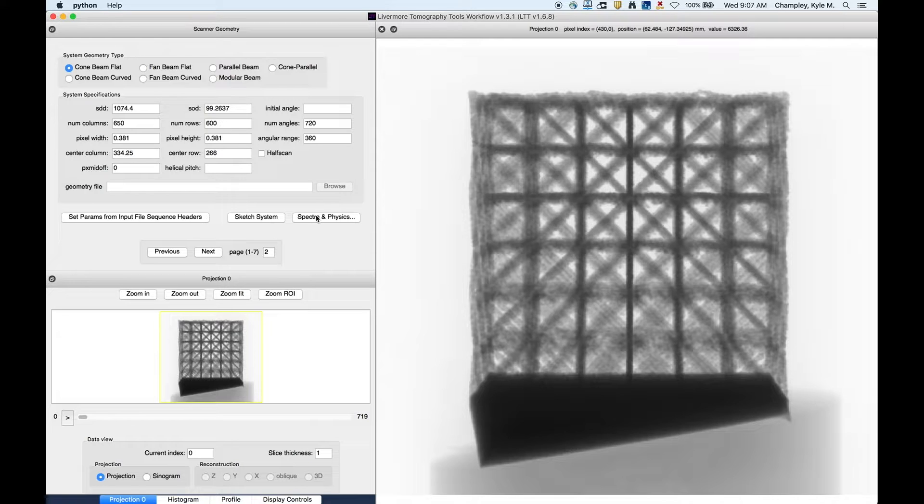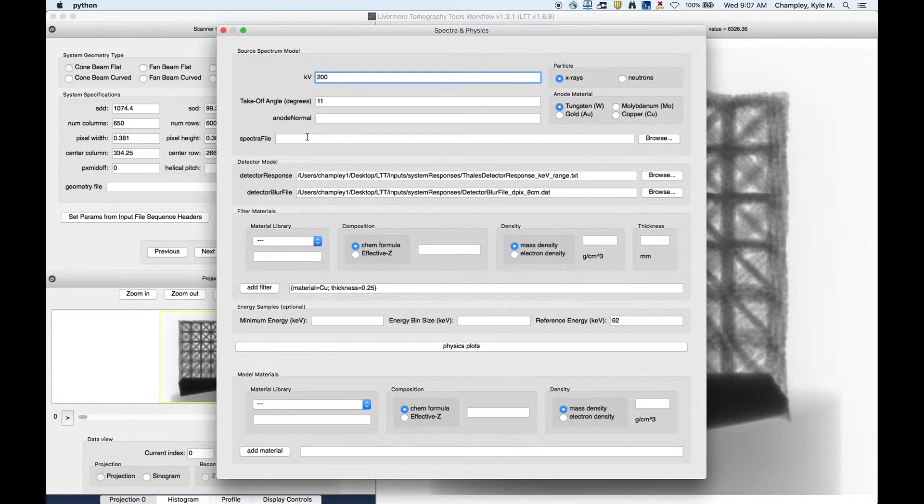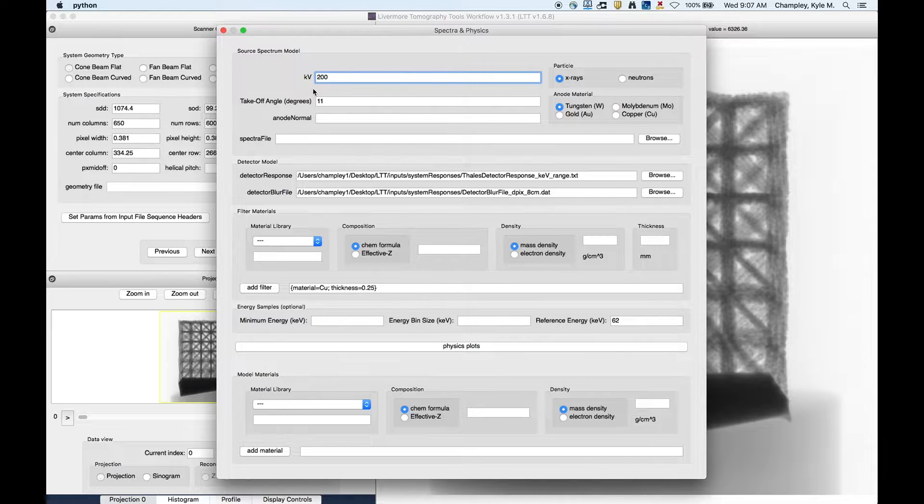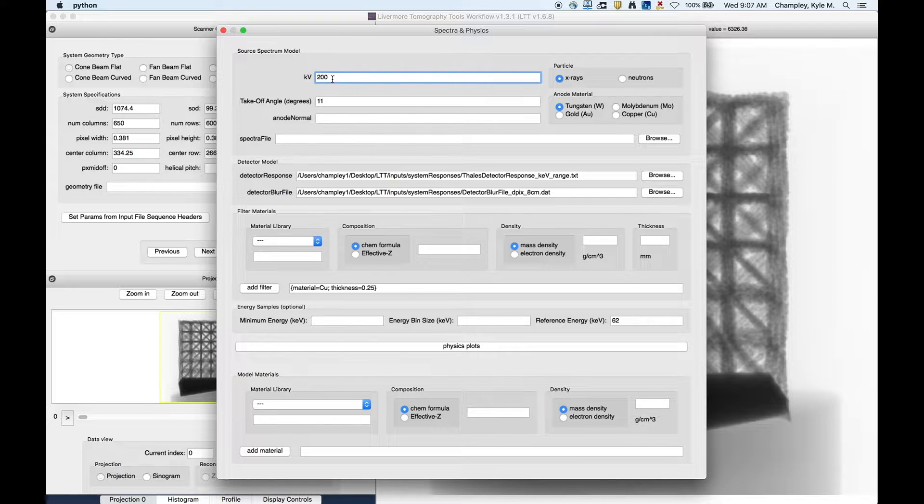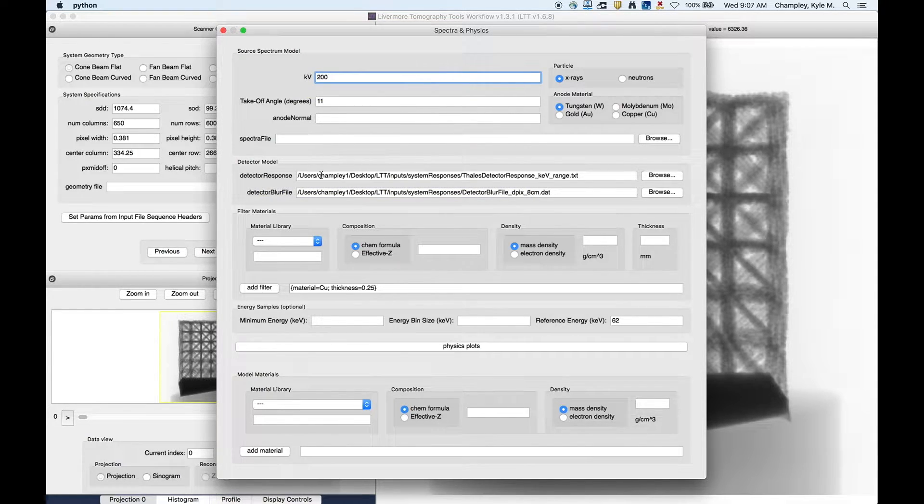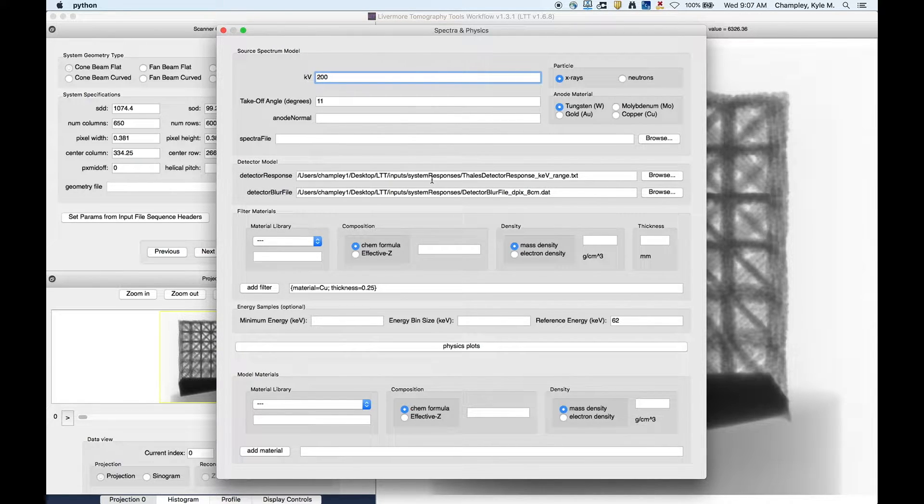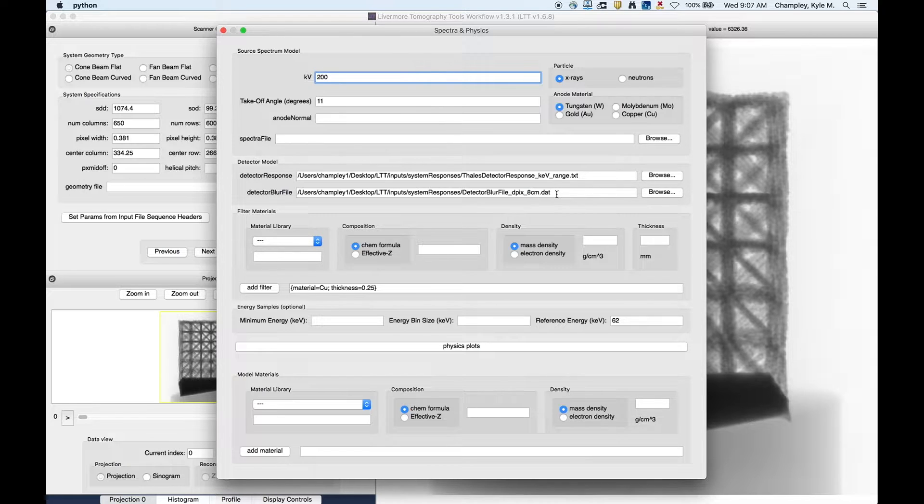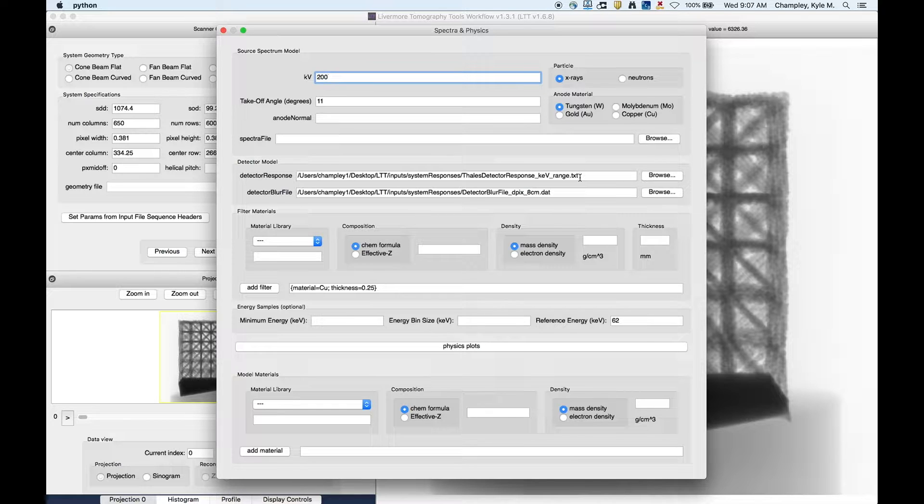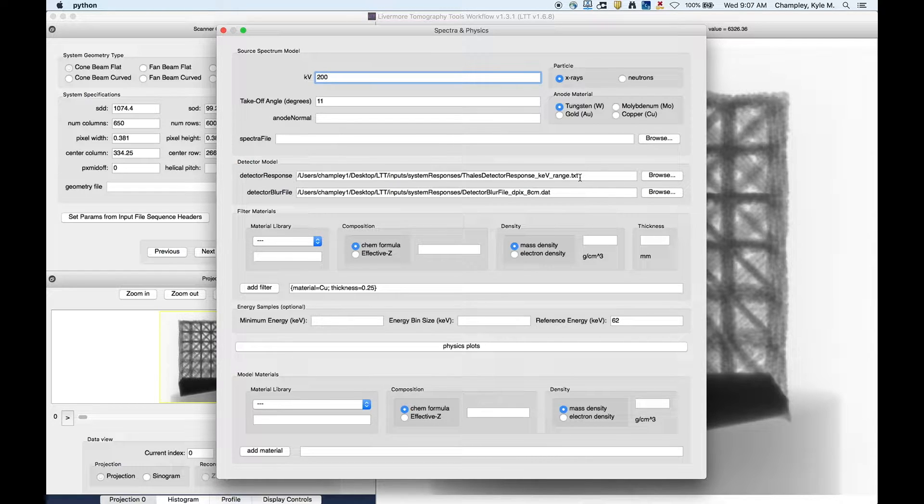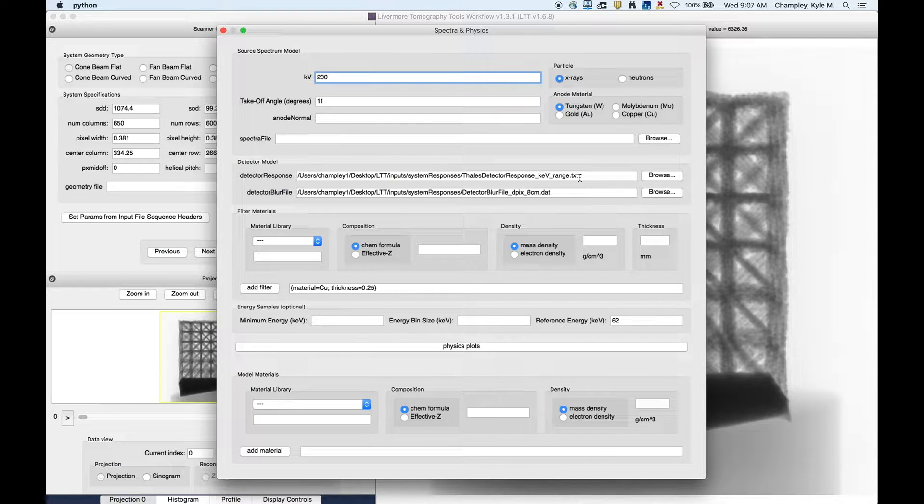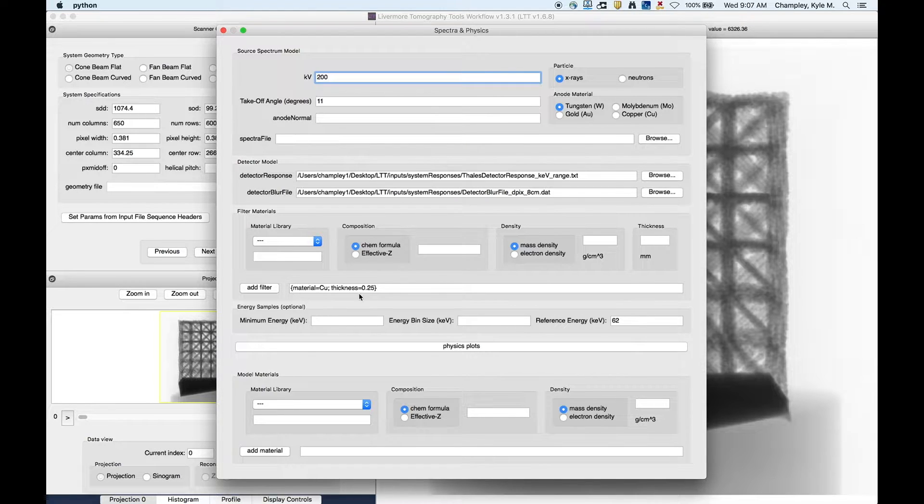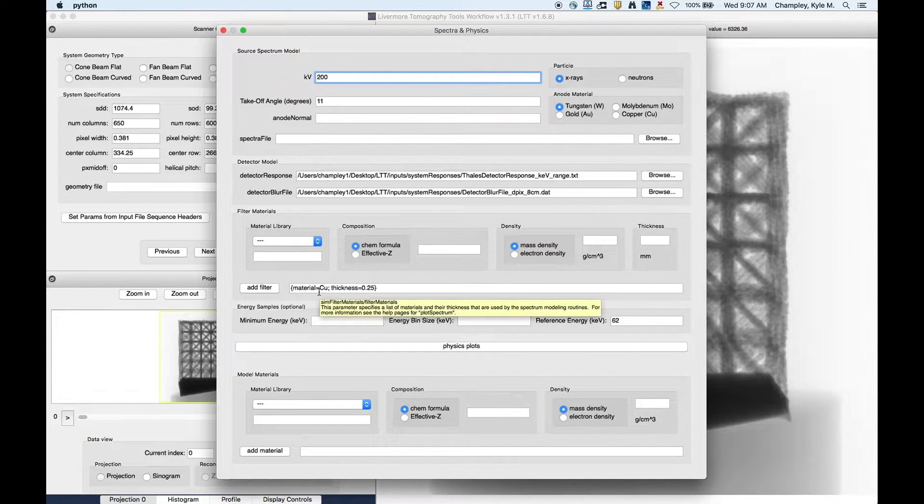We'll go to the next page, and now we're going to need to click on the spectra and physics button to make sure the entire spectra has been modeled. So here, the LTT did populate some fields. It populated KV, so it's a 200 KV. I actually put these in before, so I didn't have to find them. We have a detector response function in here. It's given by a file name, and also for the detector blur. So the formats of these are listed in the manual, and we did these with Monte Carlo simulations, but there's other ways to do these. You could do them empirically, like with stopping power. And in addition to that, in a lot of systems you're going to have to do a spectral calibration, and I'll cover that in a different video. Anyway, it looks like we have the source spectrum modeled, the detector modeled, and then for the filters, it looks like we have a quarter millimeter of copper.